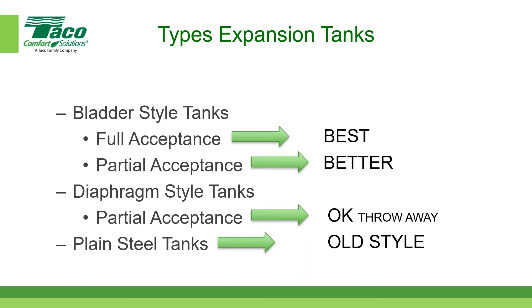To me, the full acceptance bladder style tank is the best from an engineering standpoint, from a project standpoint. Those top three, I'd rank best, better, and okay - well, the pricing is in reverse, so just keep that in mind. Most of you probably realize that, but I want to emphasize: if it's sized correctly and installed correctly, any one of them will work in your system. But once you get above a couple hundred gallon systems, 500 gallon systems in the water, full acceptance is probably the best way to go, just based on size and whatnot.